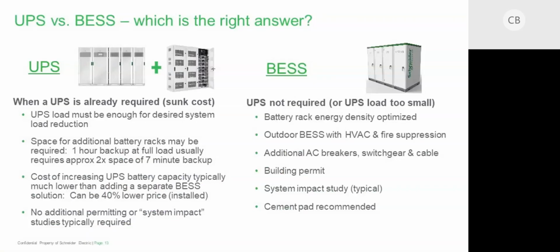When we talk about peak shaving, there are two ways to do it. You can do peak shaving with a battery energy storage solution that is independent of the batteries tied to the UPS, or today with this new offer, you can utilize the batteries on the UPS system to do some peak shaving. Now, being in the data center world, my first thought would be, hey, I don't want to use the batteries in my UPS system. That is there to back me up in case there's a power outage and I need that ride-through time until my generator comes online.